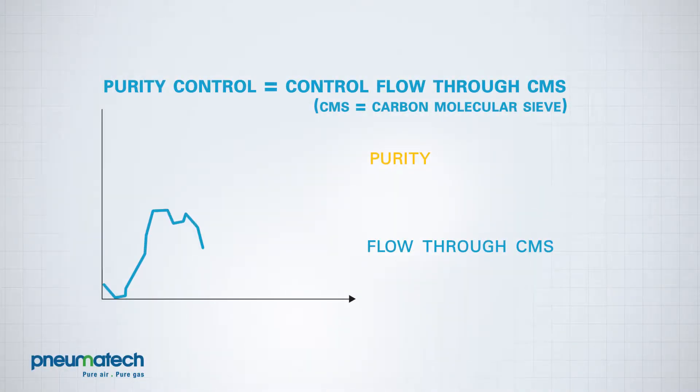The purity we achieve with the nitrogen generator depends entirely on the flow. Low flow results in high purity, while high flow reduces the purity.